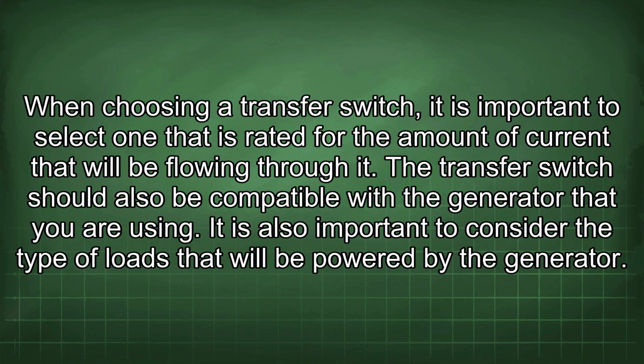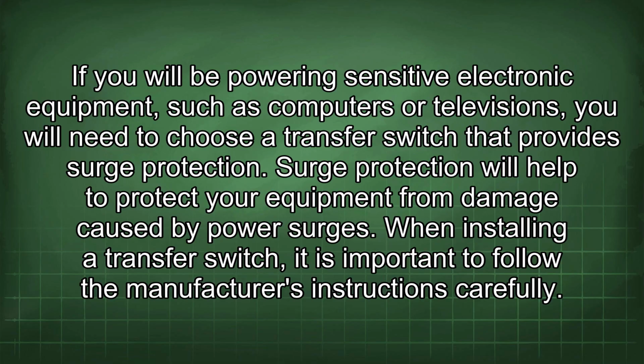When choosing a transfer switch, it is important to select one that is rated for the amount of current that will be flowing through it. The transfer switch should also be compatible with the generator that you are using. It is also important to consider the type of loads that will be powered by the generator. If you will be powering sensitive electronic equipment, such as computers or televisions, you will need to choose a transfer switch that provides surge protection. Surge protection will help to protect your equipment from damage caused by power surges.